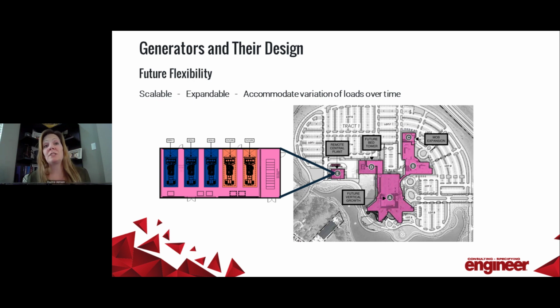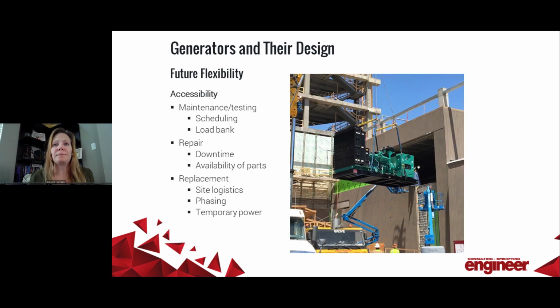A parallel generator system will allow for such flexibility as long as it's thought through at the forefront of the design. So you need to be able to accommodate the varying loads over time. So running not only the load analysis, but the future anticipated load analysis will allow you to properly size your generator plant.